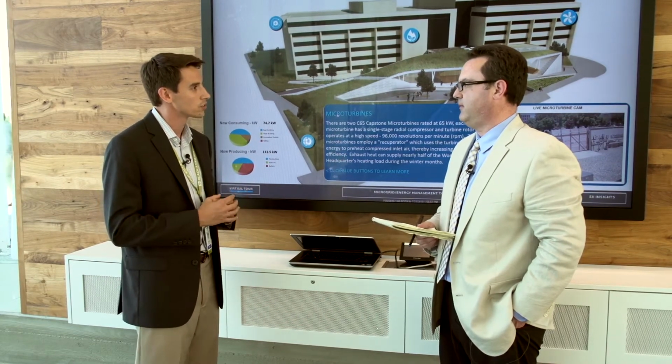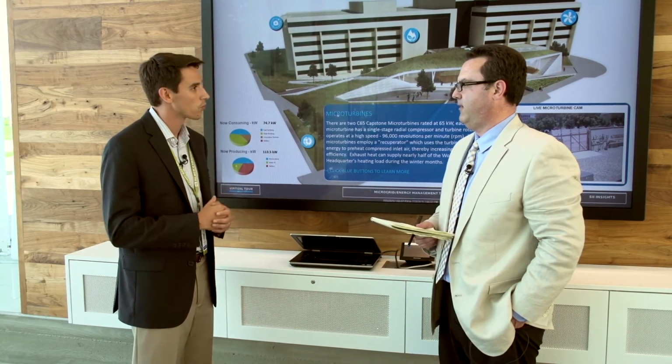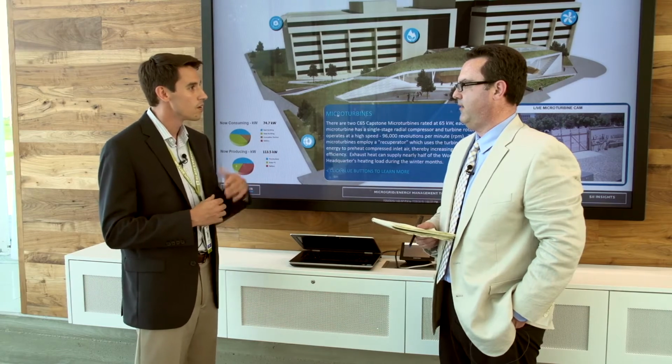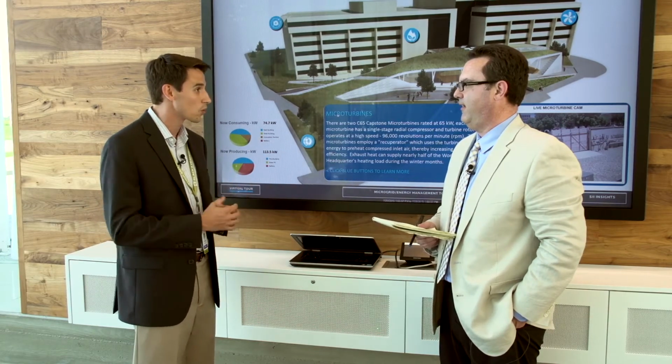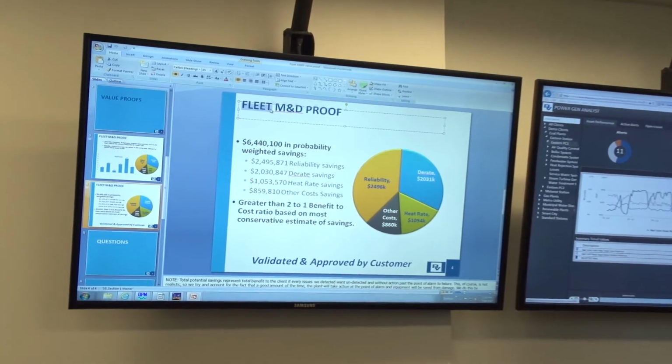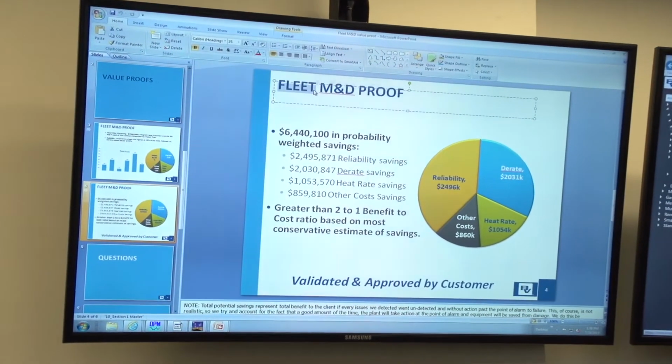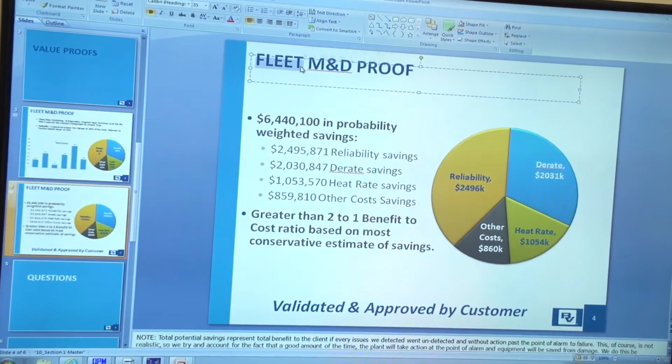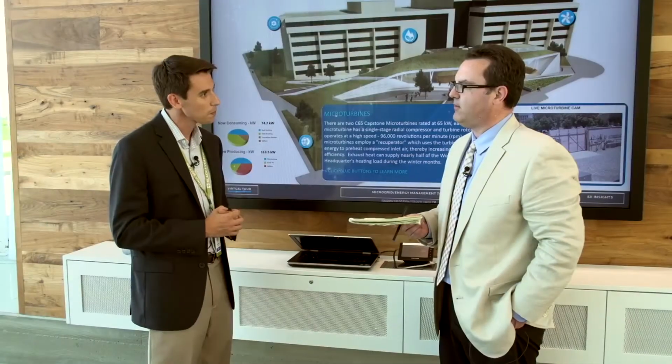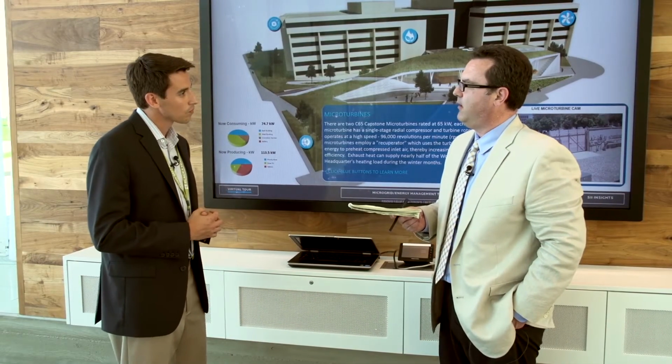We pull that in, and through diagnosing issues that come up through variables that move, heat rate calculations that move, or certain performance calcs that we perform, whether it's on a pump or a coal mill, or even a solar plant or a wind turbine, we're able to tell the client about an issue before they even get an alarm on it.